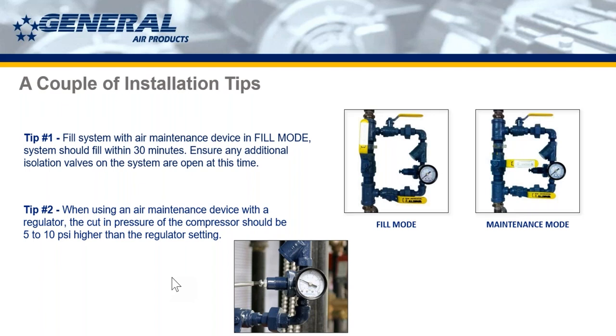So what it does is essentially make sure that the volume of air on the compressor end is holding more than it would normally, and it's going to make sure that that compressor doesn't run as frequently. And again, if the compressor doesn't run as frequently, we're not adding to the overall hours on the motor, which means the compressor can last longer, which is what we want to see.